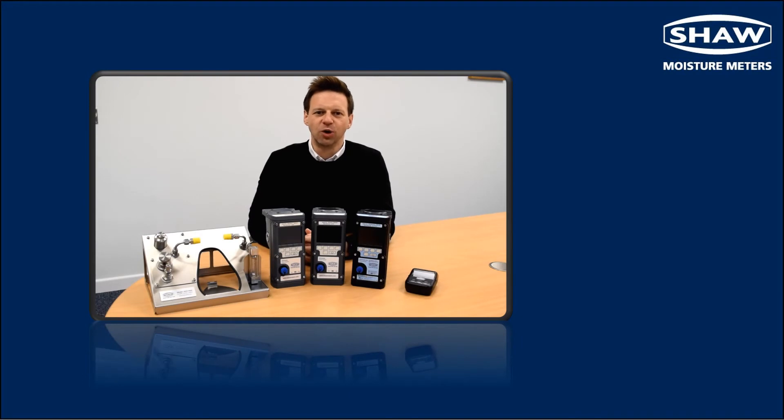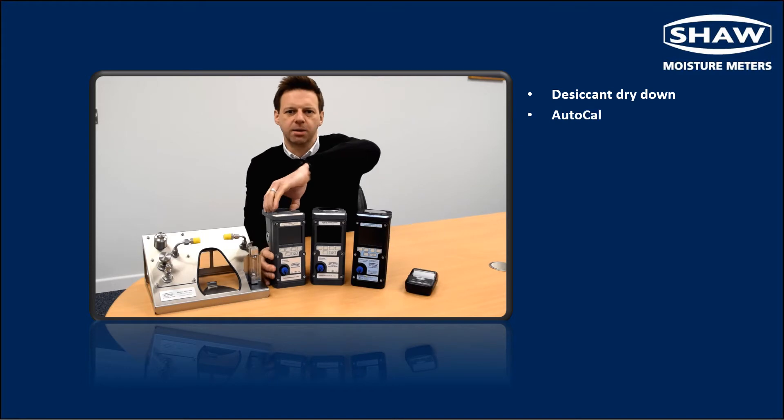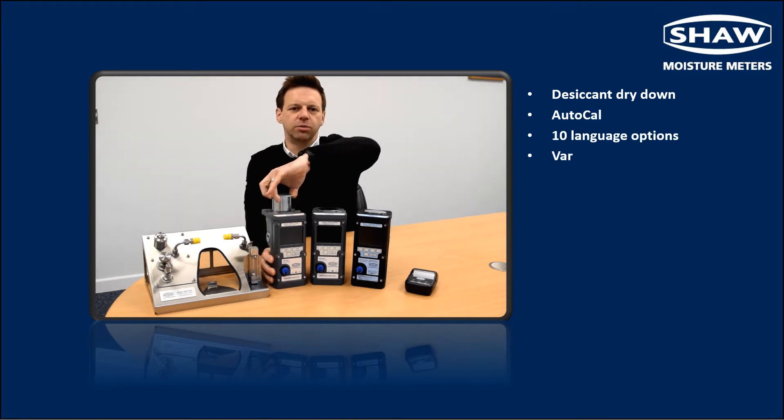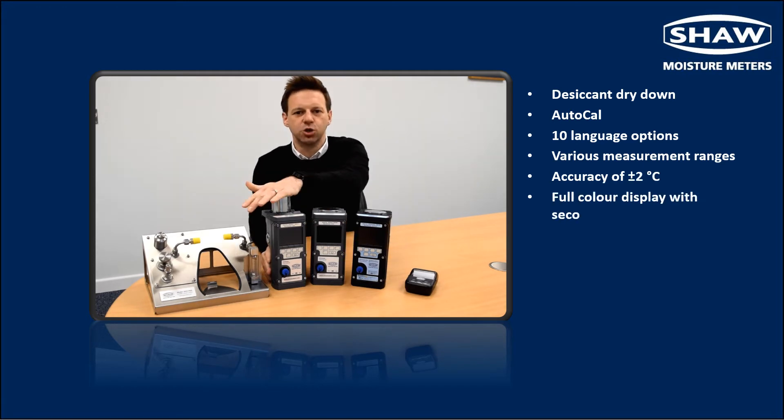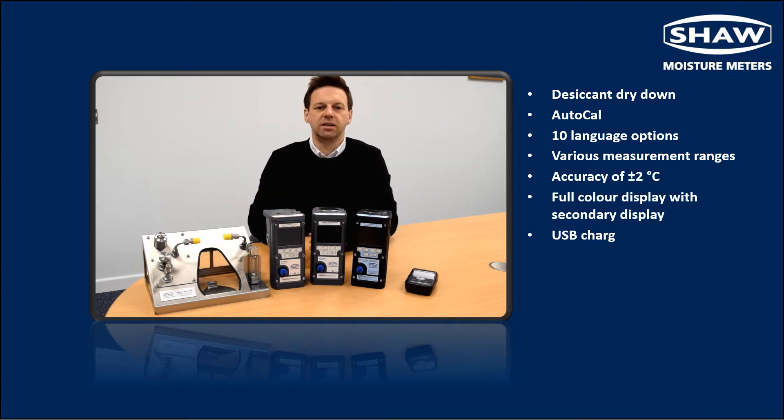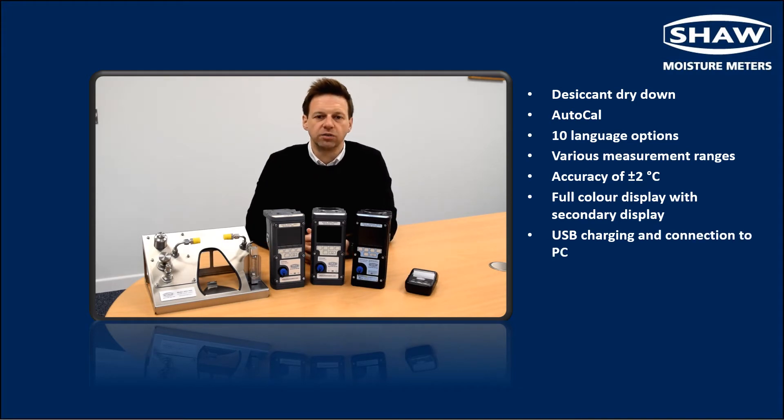In this section we're going to look at the SDH mini handheld portable dew point meter in more depth. The first two features will be familiar to anyone who has used Shaw Moisture Meters products. The first is the desiccant dry down assembly which means that the sensor is always operated from dry to wet, increasing the speed of response and ensuring that the sensor is never in contact with ambient conditions, keeping the sensor dry between tests. The second is the AutoCal feature which allows for the periodic span check and correction to ensure optimum accuracy between factory calibrations.